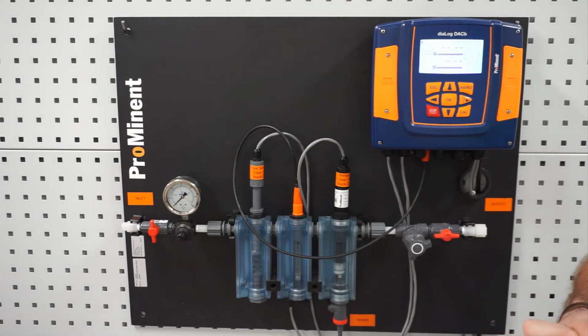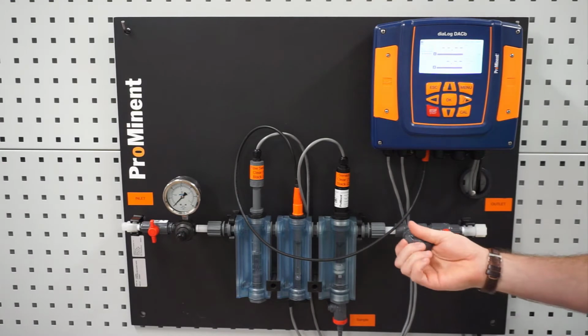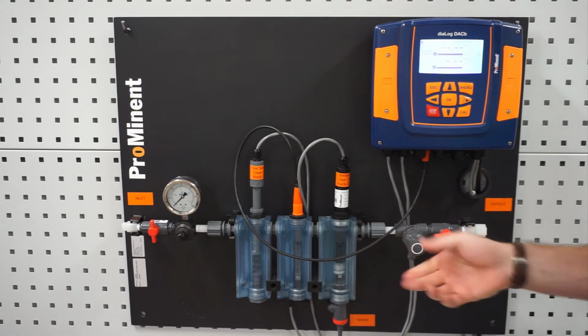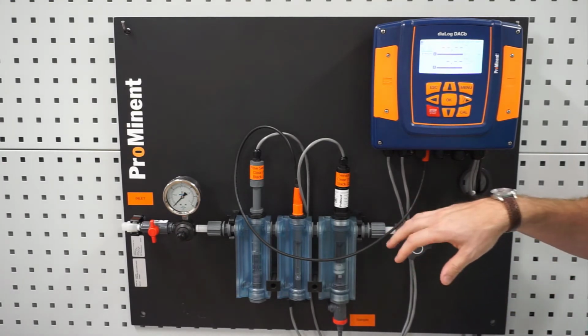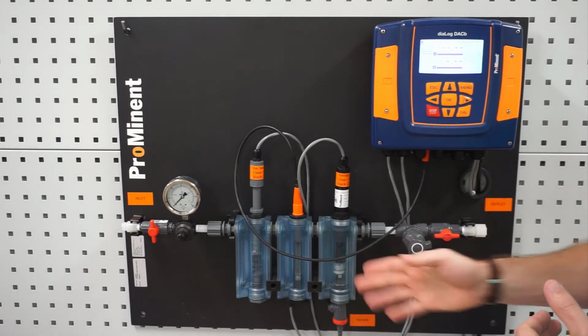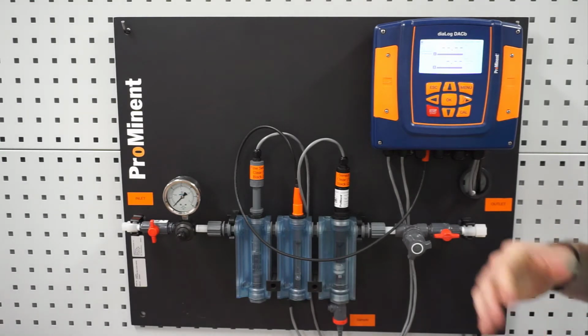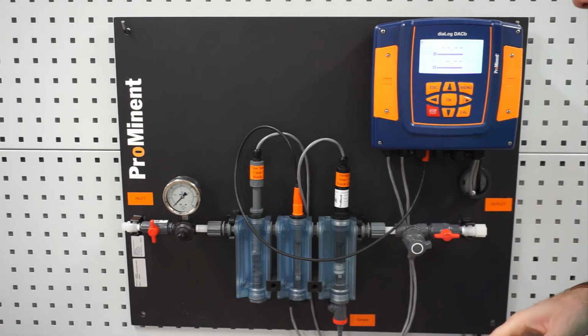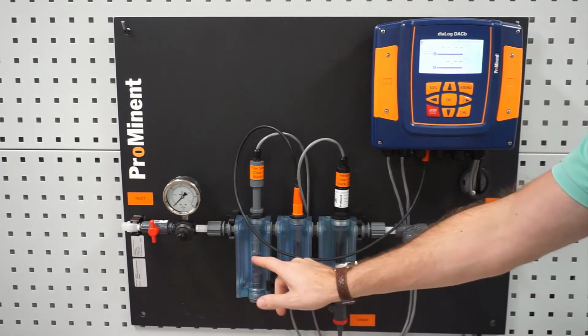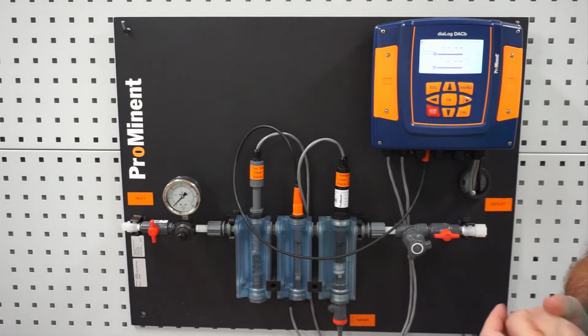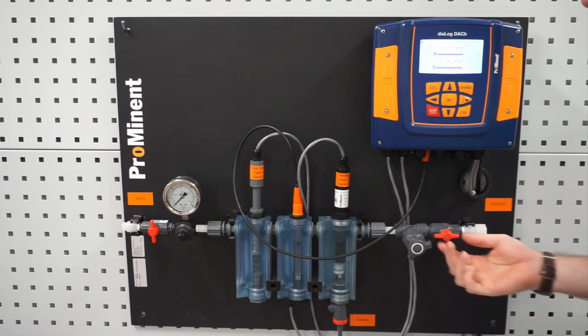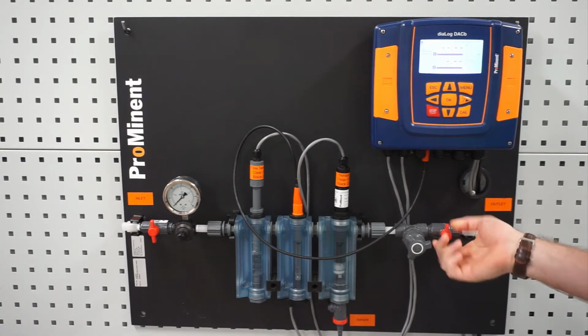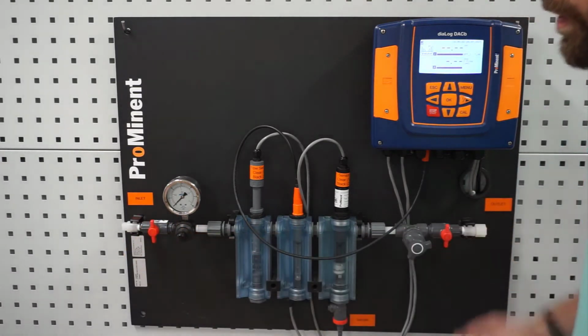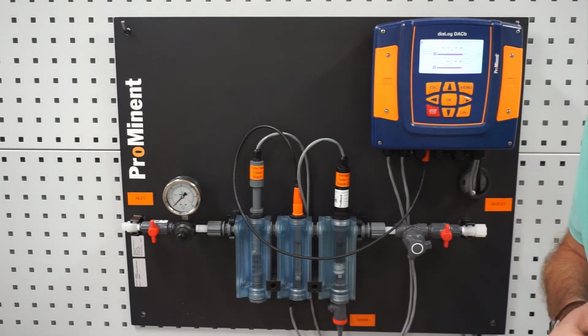After you've gelled up your free chlorine sensor, your next thing after that is going to be a needle valve. That needle valve is going to be where we adjust the flow. Our chlorine sensor is very sensitive to the amount of water that is going by it and also the pressure, like we discussed. So this is where we're going to adjust our float on our flow cell, and we'll discuss what that needs to be set at. And then lastly, we have another isolation valve, so we can lock the water in this and maybe move it to another place if we want to.